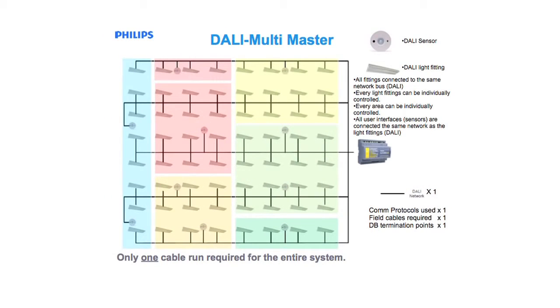DALI MultiMaster connects all the ballast and sensors to the same network. This system utilises the existing DALI cable for all the lighting network devices to communicate to the load controller. Sensors will detect activity within their area and report that back to the load controller. The load controller will then decipher the message and perform the appropriate action. If required, instructions could be sent to the ballasts on the same DALI universe and a network message sent on the Dynet network for other devices to respond to.